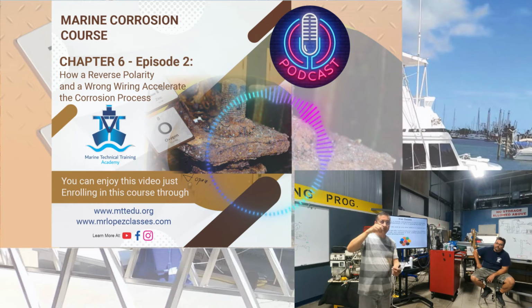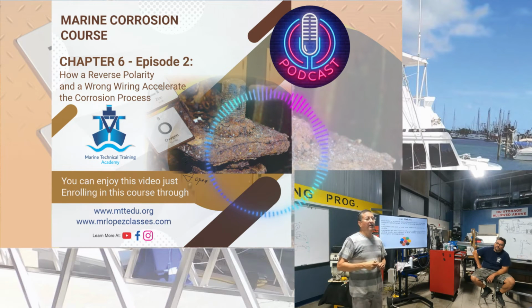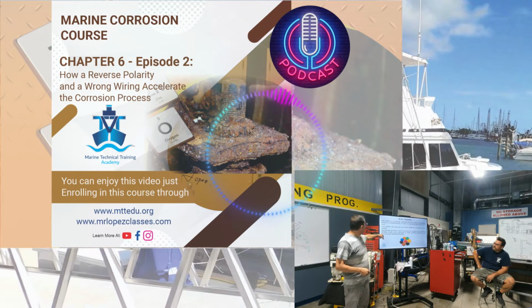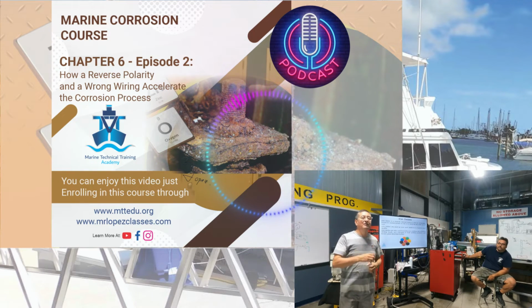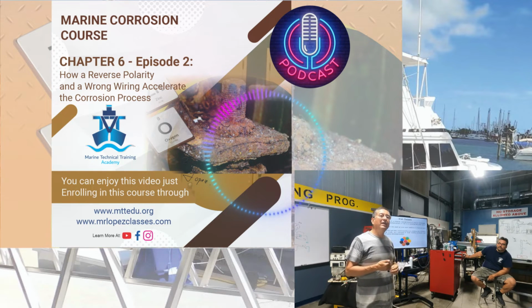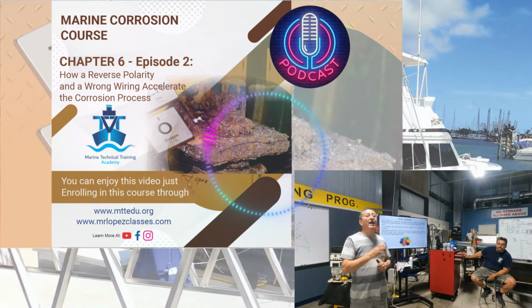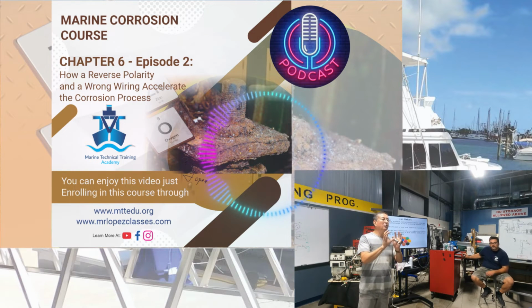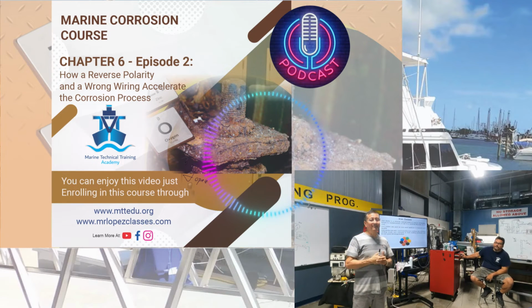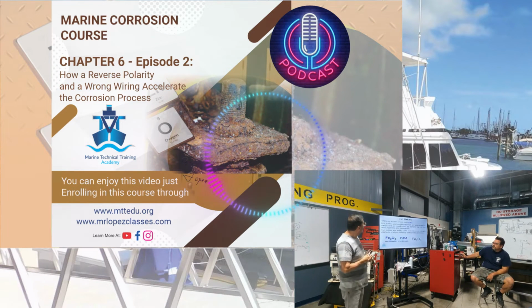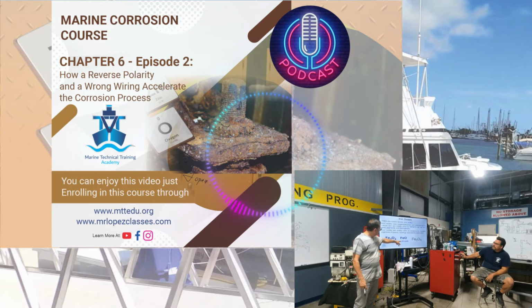Right now, I am going to connect the neutral of this with this, and the neutral of this with this. All of the neutrals are connected together, and from one of those connections, this is the neutral passing to the isolator transformer, continuing, and entering the panel: the neutral bus bar and main breaker. After the main breaker, the hot line enters the hot bus bar, and this is the output of the breaker. This is the output for lights, this is the output for outlets, and this is the output for the battery charger.